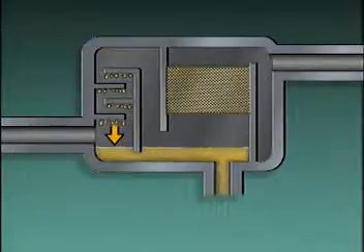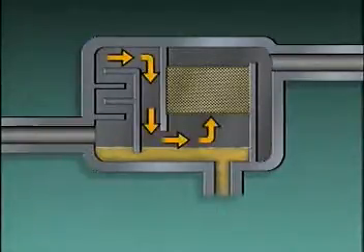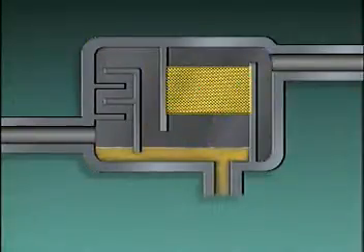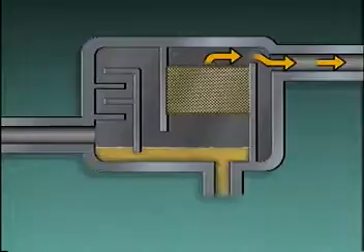In this way, most of the oil is removed from the gas. After the gas passes the last baffle, it flows through the wire mesh screen. Most of the small amount of remaining oil is trapped by the screen and then goes into the sump. The relatively oil-free gas continues on through the outlet.